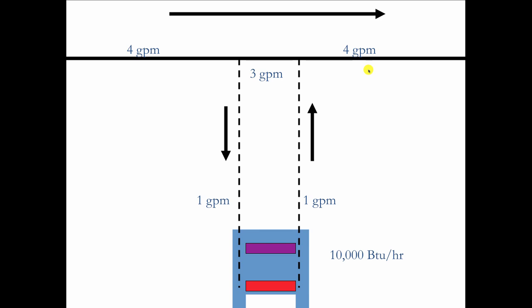Now supposed to make that happen, the manufacturer says you must use two of these Diverter T's. One pointing one way, the other pointing the other way. But the builder figures he wants to cheat a little bit, so he says, what if I leave out one of these T's? Who's going to notice? All the walls are going to be closed up. So he does that. Now if he leaves out one of the T's, you're not going to have as much pressure drop along this primary flow. So you're going to get more than 3 GPM here, right?